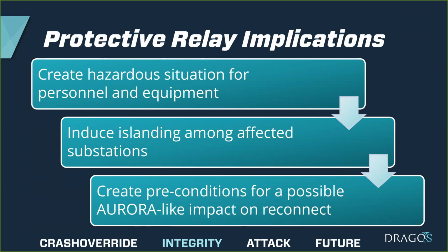It's almost something similar to the cascading effect seen in the 2003 Northeast and 2003 Italian blackouts. Or even more scary, when we talk about protective relays in the context of generating equipment, you're creating preconditions for possible Aurora-like impacts on reconnect. The Aurora test was the U.S. Department of Energy Idaho National Laboratory test that showed, through modifications to how timing works with protective relays tied to generating equipment, you can cause it to lurch back and forth and create physical damage within a relatively short period of time. So mucking around with protective relays can lead to very interesting and very serious consequences rather quickly.